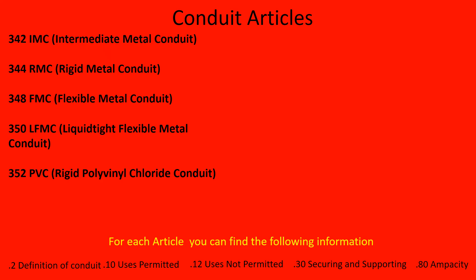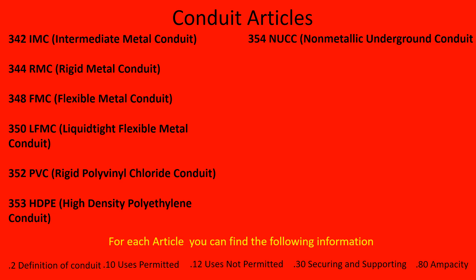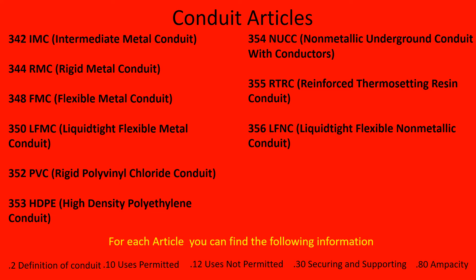Article 352 is rigid PVC, polyvinyl chloride — your schedule 40s and schedule 80s. 353 is HDPE, high density polyethylene conduit. 354 is NUCC, non-metallic underground conduit with conductors — it has the conductors inside of it, so that's one that may have a dot 80 section. 355 is RTRC, reinforced thermosetting resin conduit. 356 is LFNC, liquid tight flexible non-metallic conduit — that's what we call CarFlex.